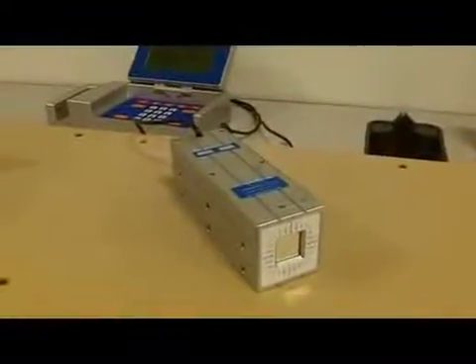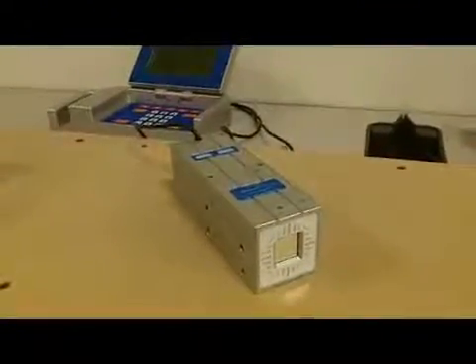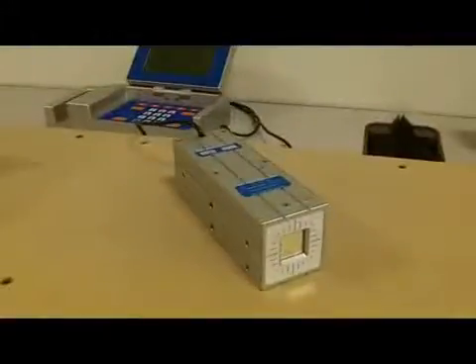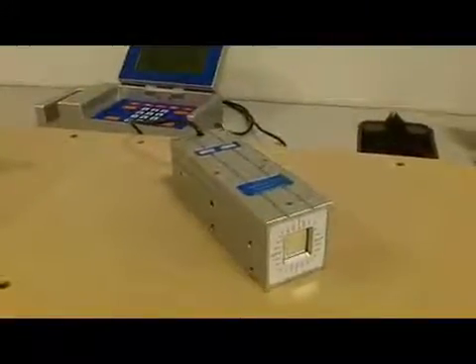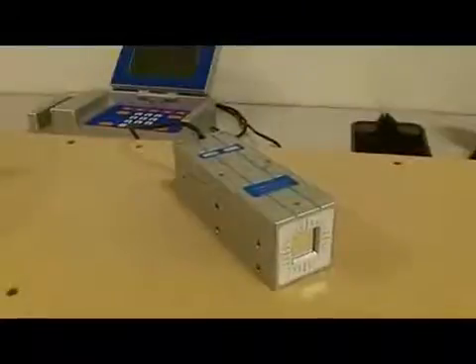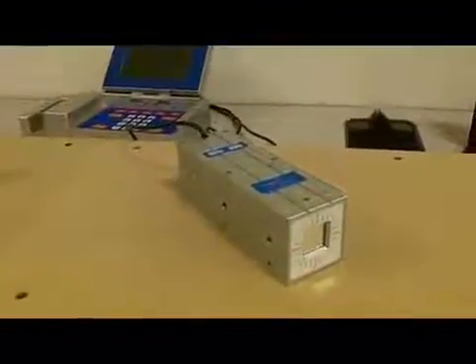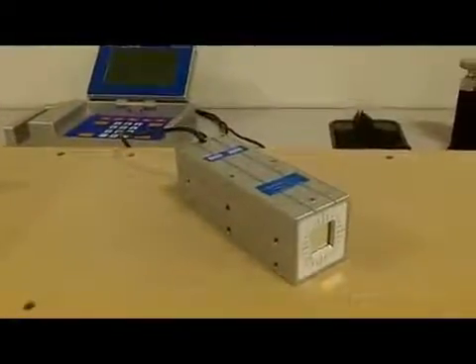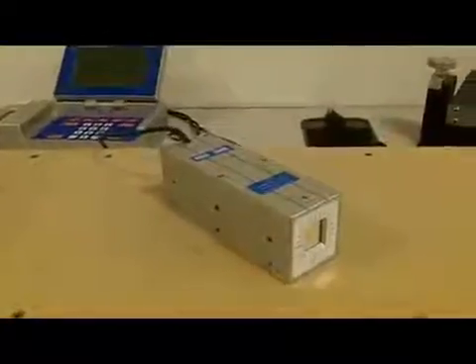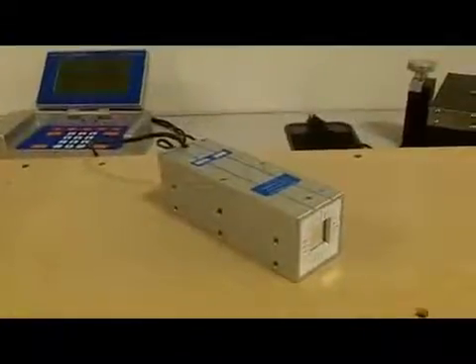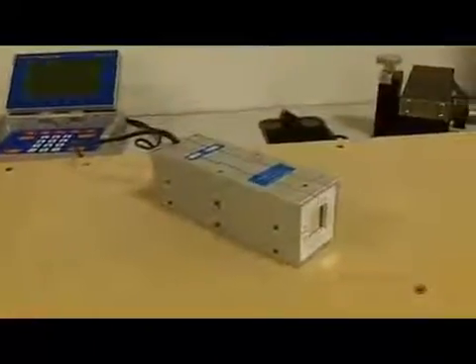The microgauge 4D receiver is one of the many accessory items offered with Pinpoint's extensive line of laser alignment products. The 4D receiver is an enhanced version of the standard microgauge 2D receiver in that it not only provides both vertical and horizontal alignment information, but also two angular components, pitch and yaw.